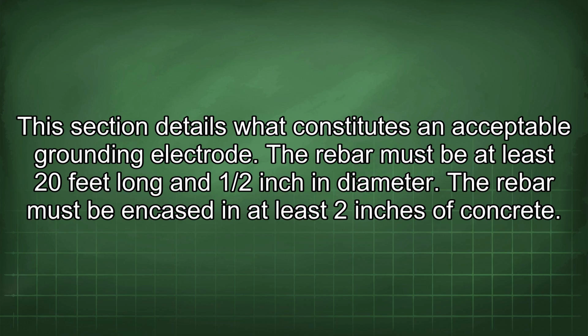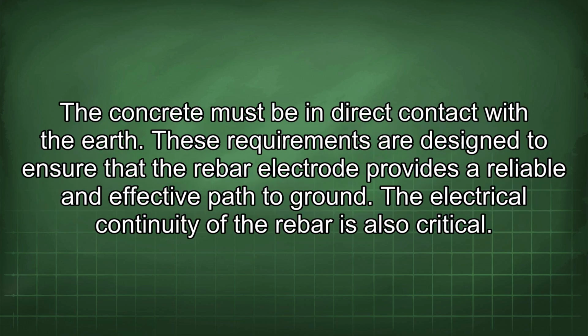The rebar must be encased in at least 2 inches of concrete. The concrete must be in direct contact with the earth. These requirements are designed to ensure that the rebar electrode provides a reliable and effective path to ground.